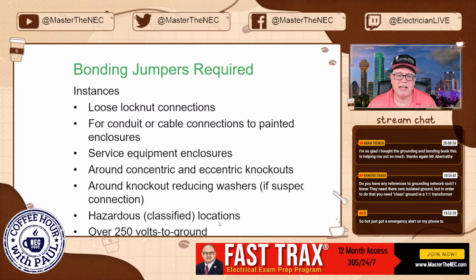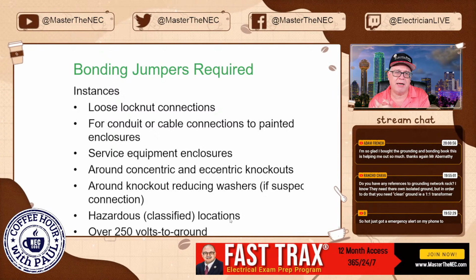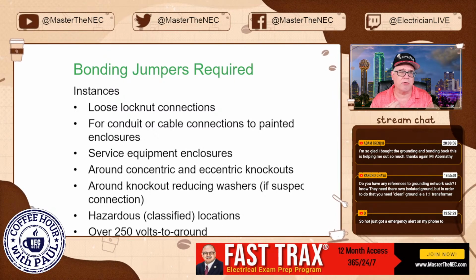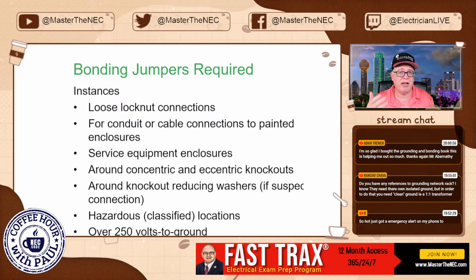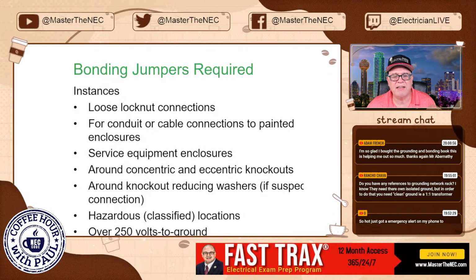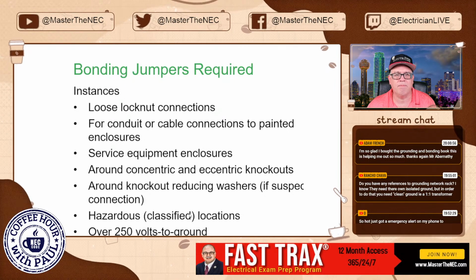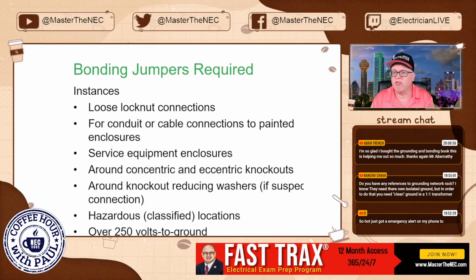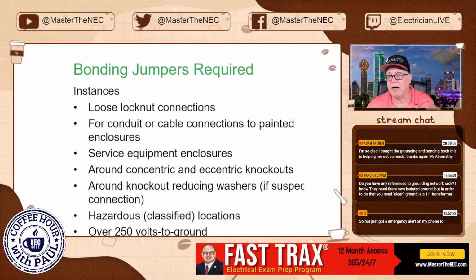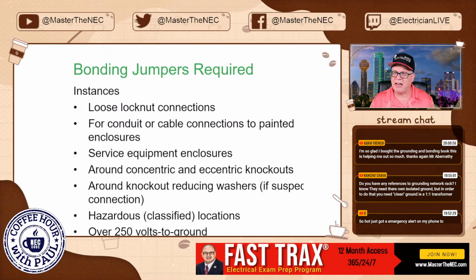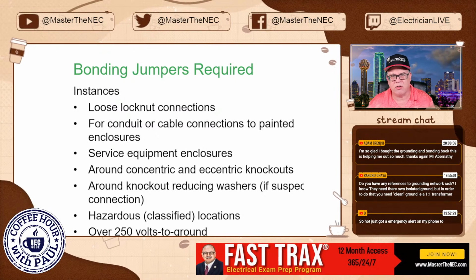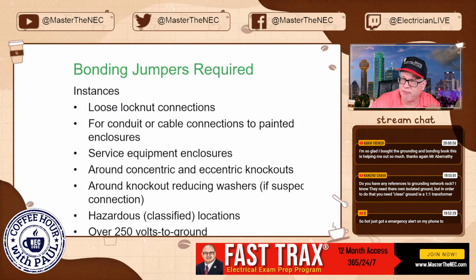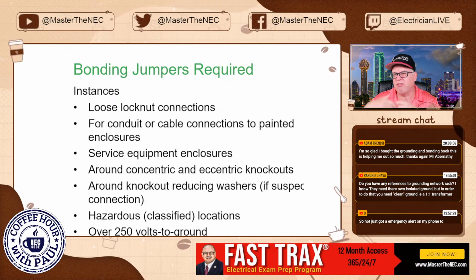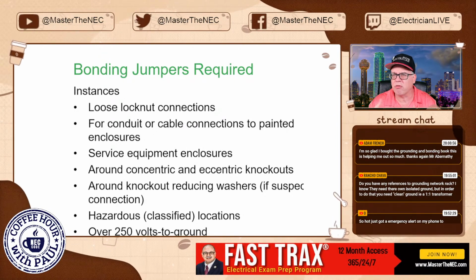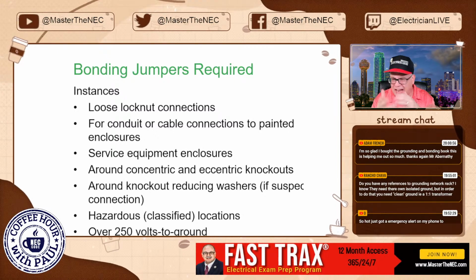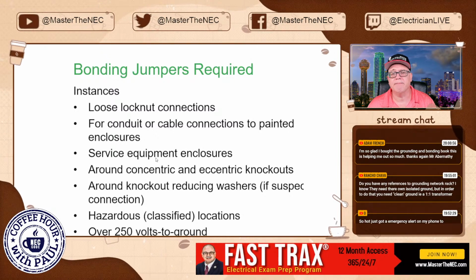Hazardous classified locations, again, are heavily going to require bonding jumpers. Like we talked about earlier, we're not going to rely on potential loose connections that could create an arc, things like that. And then, of course, anytime you're dealing with over 250 volts to ground, the code is going to require bonding jumpers for that as well. Of course, there are some nuances. You have things like bonding wedges if you remove all the KOs, or you might have a box that's already rated for over 250 volts. Then you have some allowances there, but we're just talking in general. These are instances where, if you had any of these situations, a bonding jumper would be required.